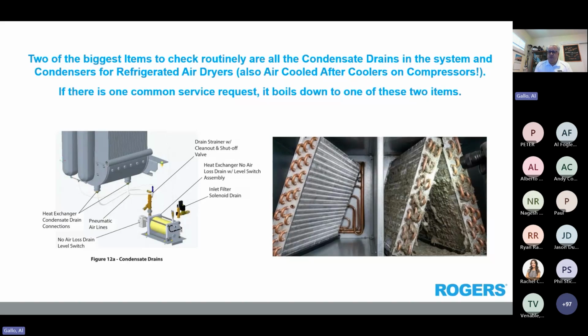Just a quick test. Most of them have a test button, either electronic drain valves, like what you see pictured on the left, or the pneumatic no-loss drains. They have a test button or a switch to hit to check it, just to make sure everything is working. And then those two condensers on the right side, which one do you think is going to work better for doing what you need it to do? And it also applies to the air-cooled aftercoolers on compressors. In Colorado, we get a lot of cottonwood trees at this time of year, and they plug up these coolers so fast. So just be aware of that.